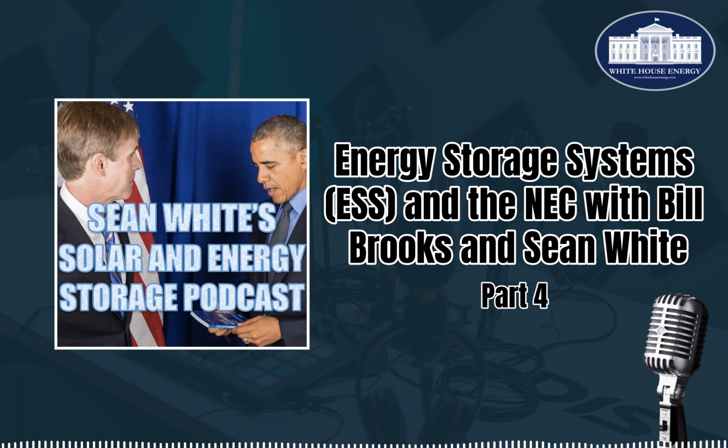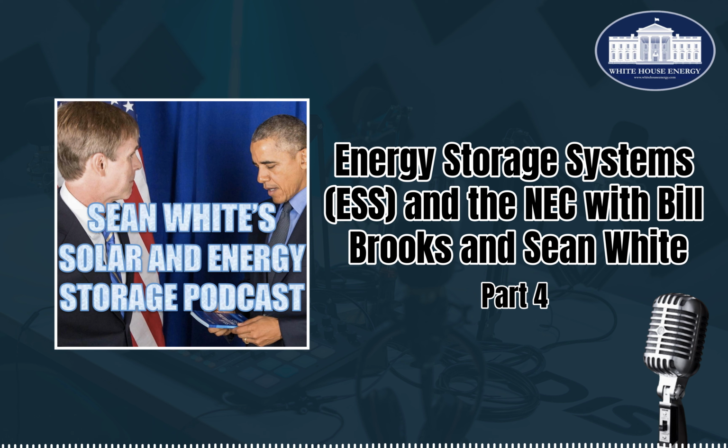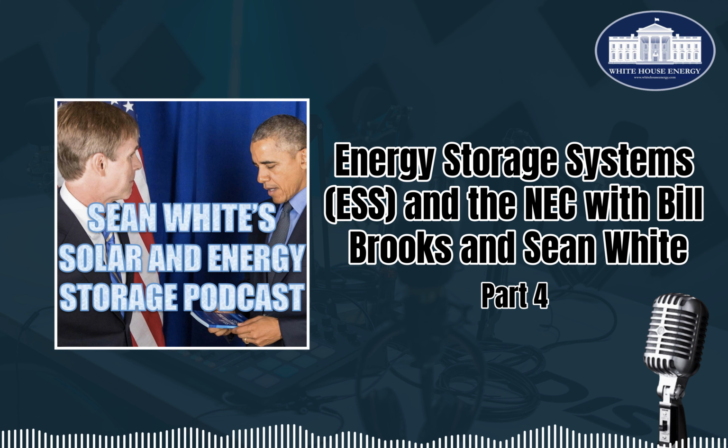You would tend to put it at the top of the panel because that's where there are typically more breaker spaces available. But you also may have an extra space at the bottom and only two extra spaces at the top. So that's why splitting them up may just be simpler, so you don't have to go rewire your entire distribution panel. Multi-ampacity bus bars. So this is the one where it says we can do things under engineering supervision.